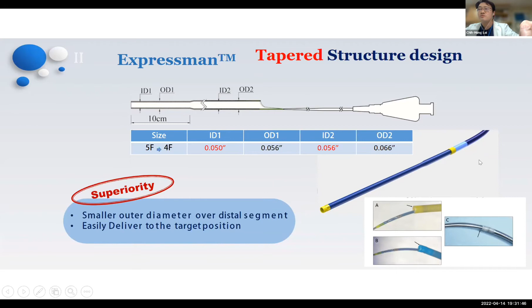Therefore, they can be advanced to the more distal segments. And the much smaller distal tip can eliminate the gap between our guide wire and the extension guiding catheter, to make our delivery much smoother. So this taper one has a distal 4-French outer diameter. The inner diameter is only 0.05 inch, around 1.27 millimeters in diameter. So it's much smaller, even smaller than the Guideliner 5.5 compatible guiding catheter.